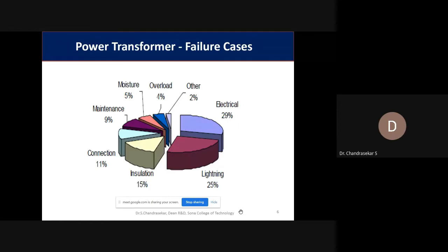The next major one is failure due to insulation, which is almost 15%. Fifteen percent means that with thousands and thousands of transformers located all over the country, if 15% fail due to insulation, then we need to give much more importance and focus to the insulation system. That's why I told you that whenever we are dealing with the high voltage side, we need to concentrate more on the insulation that is used.